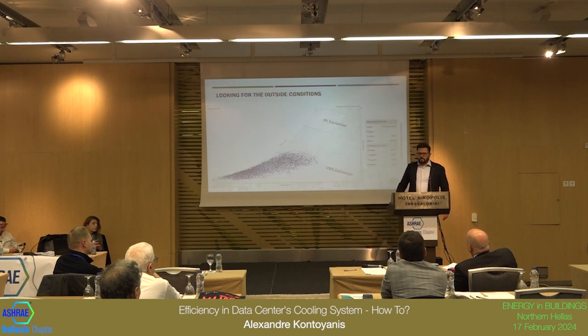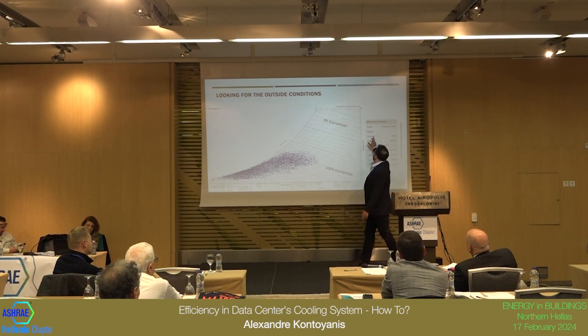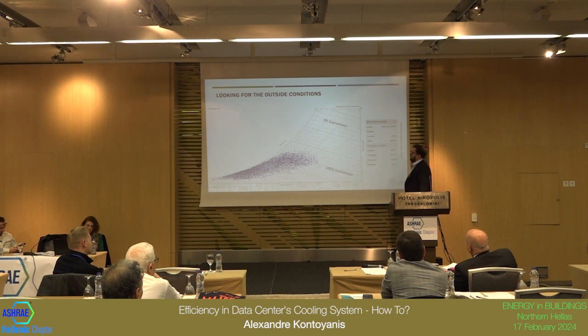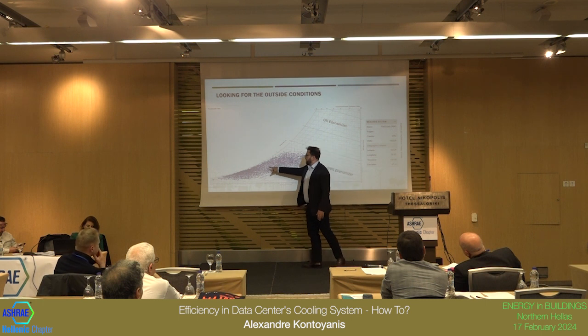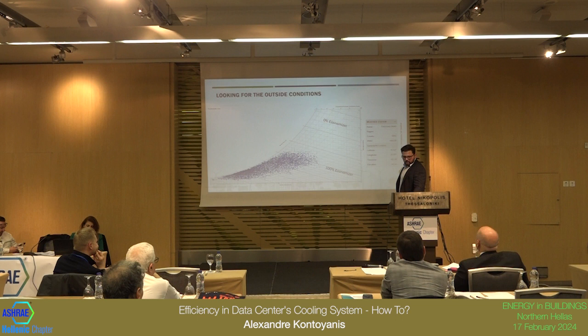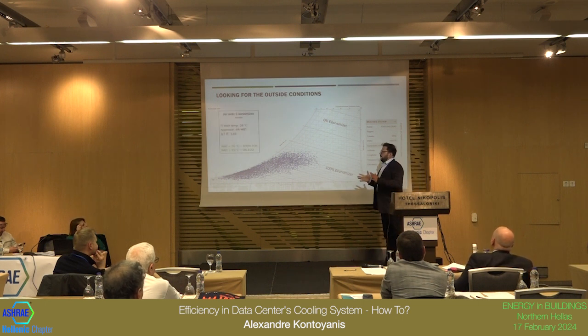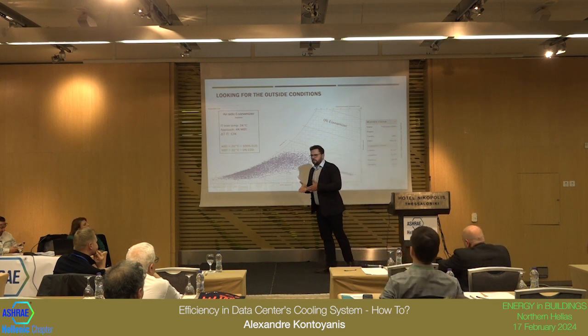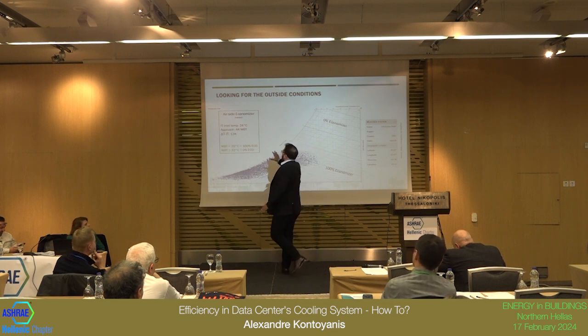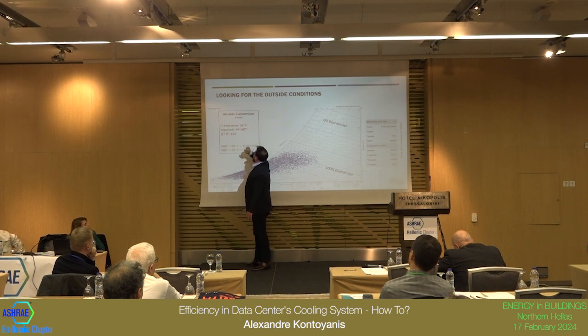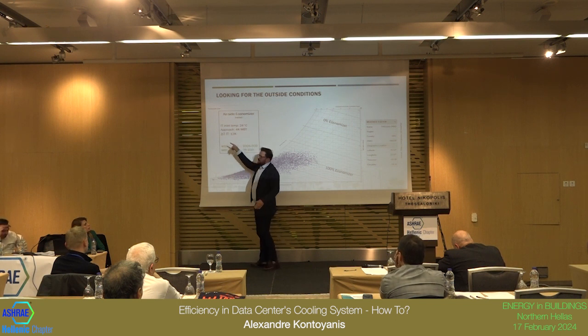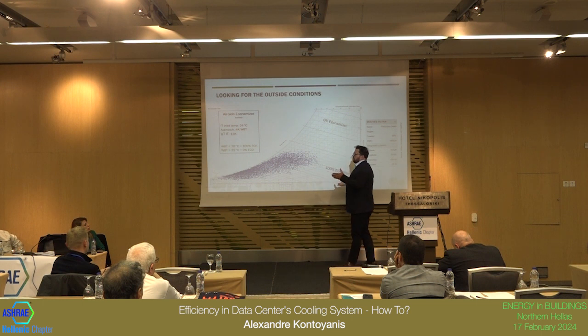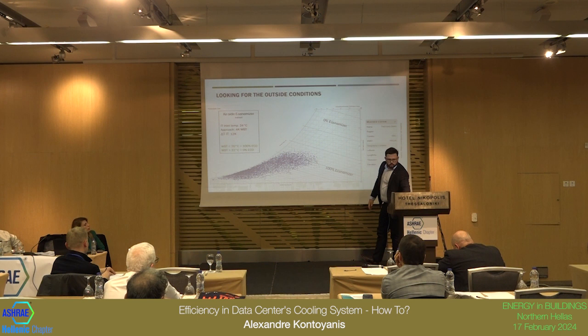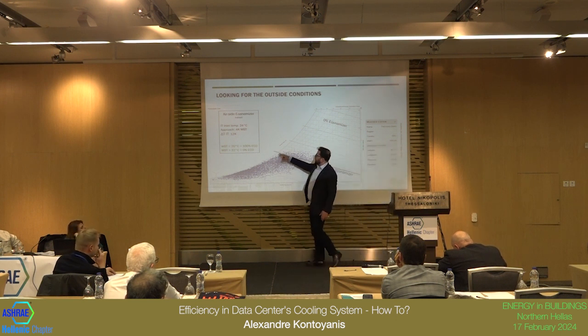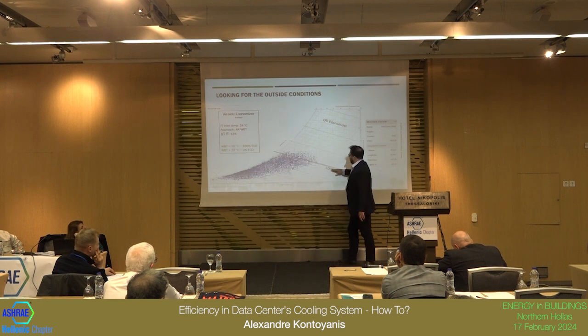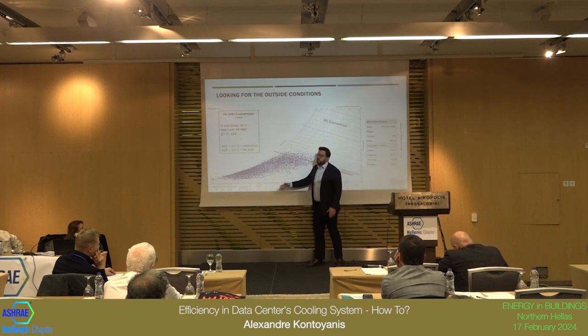Let's see outside conditions. These are conditions for Thessaloniki. I took them from the EnergyPlus website. Each point is an hour of Thessaloniki weather. We look at this and we draw some lines. For example, I want 24 degrees Celsius in my data center. It's okay for the standard, which is between 18 and 27. I bought very efficient indirect airside equipment, so it's 4K of approach. I have an IT delta T of 12. It's very common, this rise of temperature across the IT equipment. What we see is that below this line, at 20 degrees Celsius dry bulb temperature, all those points, all those hours in Thessaloniki, we could do without chillers.